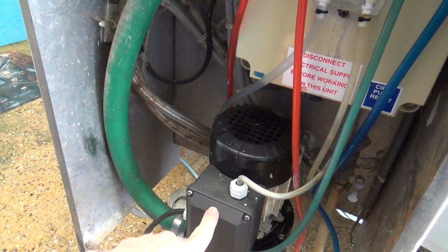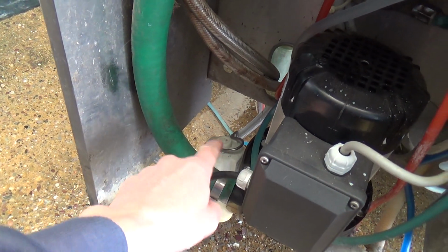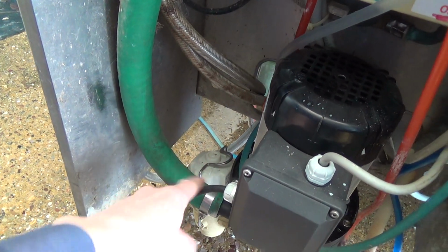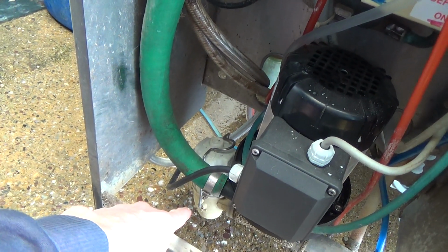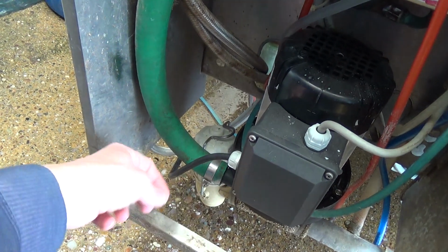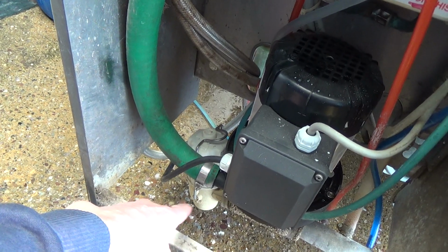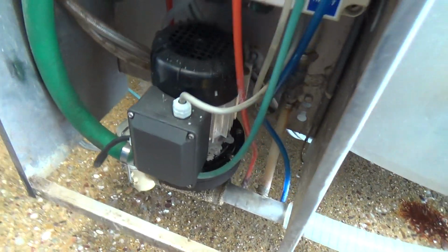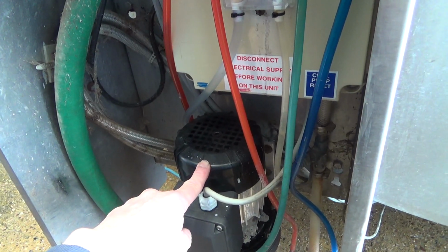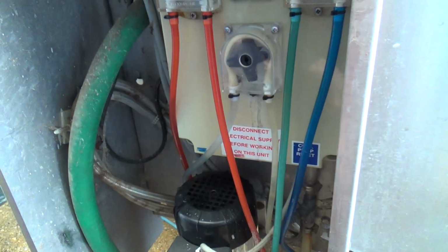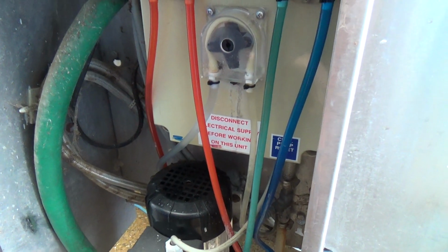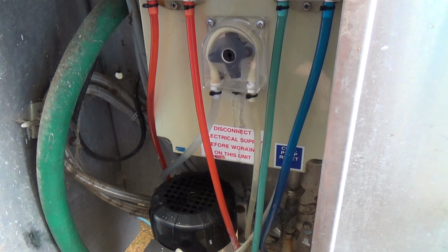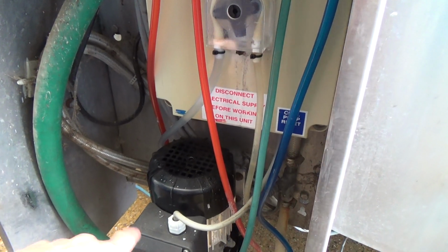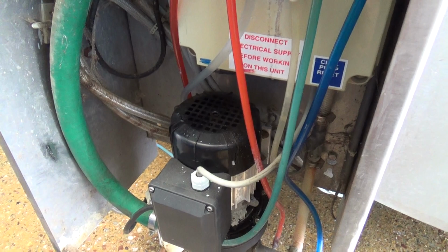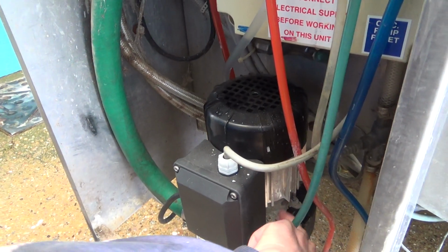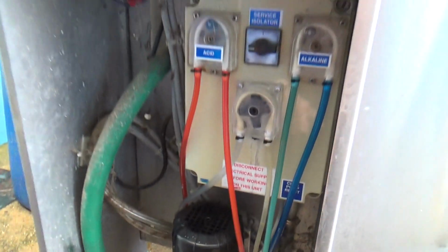So we can Megger everything, because the favourite thing to go is the dump valve. If it's an earth fault, they used to be quite common, although they've got better. Nowadays it's usually the diaphragm goes. I think they've banned a chemical they used to put in the rubber diaphragms to make them more pliable, flexible, and now they just rot basically. So that's a favourite. That pump could be it. And then we've got hot and cold solenoid valves that I have had short out, but they're rare. If they go, they usually just burn out rather than short to ground. That pump's new, so I'd hope it wouldn't be that, because that's still under warranty. Although looking at that, it's getting quite a crust on there already. Anyway, let's pop the cover off and get the Megger fired up.